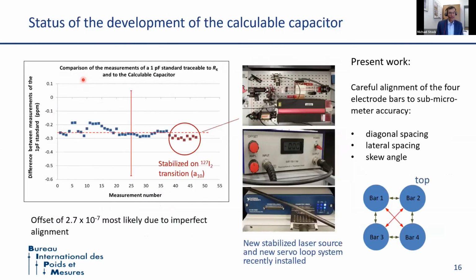We have built such a system already quite a number of years ago. This was a collaboration initially with the NMI of Australia. We did some first measurements some years ago, the blue points here. We then changed, at one point, the source for the interferometer laser, and you see that we got quite good agreement with what we had before, but we were 2.7 parts in 10 to the 7 away from the expected capacitance value, which was at that time based, of course, on the quantum Hall resistance. And it is very likely that this was due to imperfect alignment, which in fact we had at that time.